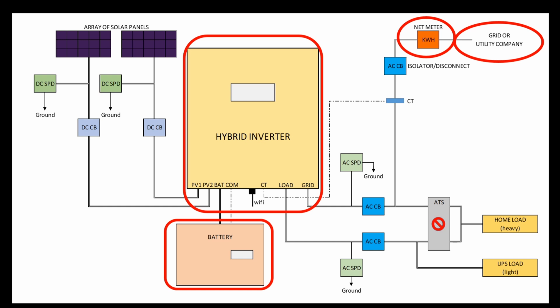The hybrid inverter has the unique feature or capability to import or export power depending on the given situation or condition. The CT, or current transformer, is a device that reads or detects current flow, whether incoming or outgoing. It plays an important role in helping us configure our inverter, or what setting to adopt at a certain time or day.